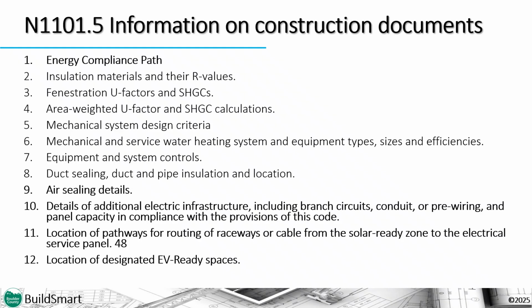So beyond including the R values and U factors for all your building assemblies, as well as the HVAC design information, which is more fully required in the N1103 Mechanical Systems section of the table, you'll need to provide air sealing details, details of additional electric infrastructure, including branch circuit, conduit, or pre-wiring, and panel capacity in compliance with the provisions of this code. Location of pathways for routing of raceways or cable from the solar ready zone to the electric service panel.